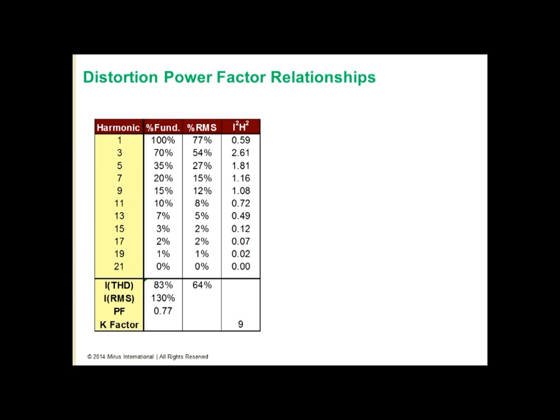Percent RMS is often the way harmonics or total harmonic distortion are described in Europe and other areas of the world. Here the harmonic numbers are referenced with respect to the total RMS value. So the third now is 54% of the total RMS value and still is 70% of the fundamental. The last column shows an I squared h squared relationship. This is what is used to determine K factor. K factor is essentially a measure of the additional losses and heating associated with harmonics in a transformer. And we use K factor values to define how well a transformer is going to be able to handle a specific harmonic load.